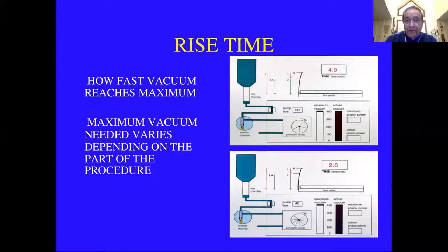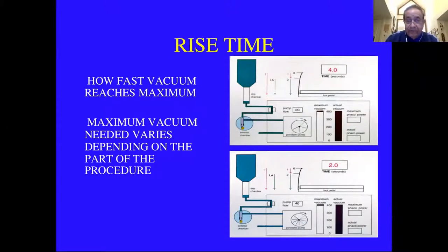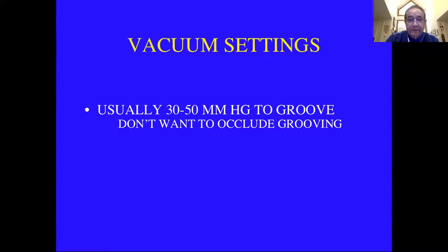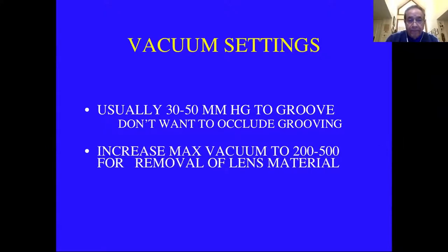Rise time is how fast the vacuum rises when you're in position two. If you're set at 20 milliliters per minute, it may take four seconds to get to your maximum. If you double the speed to 40 milliliters per minute, you should get to maximum vacuum in two seconds. You want to set it fast enough that material moves, but not so fast that it's jerky and you aspirate things you don't want, like the iris or the capsule. You have different vacuum settings and aspiration rates for different parts of the procedure. For a grooving procedure you usually only need 30 to 50 mmHg, but you have to increase it to 200 to 500 for removal of lens material.